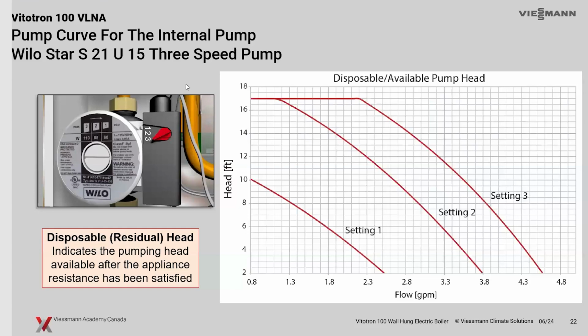And even though it's an electric boiler, it does stage. And a lot of times, just like a condensing boiler, it'd probably be beneficial to pipe these with closely spaced tees or primary, secondary, depending on your applications. But again, you've got a pump in here. It is going to have some limitations as far as what's left over, what that pump can do. So if you're really zoning heavily in your systems, for instance, that's a consideration. If you're not doing a lot of zoning in your system and you're just kind of minimizing that side of it, that tends to be a little less cycling of the boiler, that sort of thing. But you're still looking at that high pressure drop. So whatever we're dealing with there, just make sure you're fitting your system within the capabilities of this little pump.